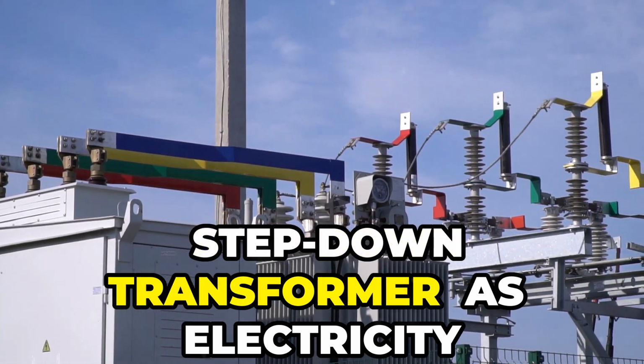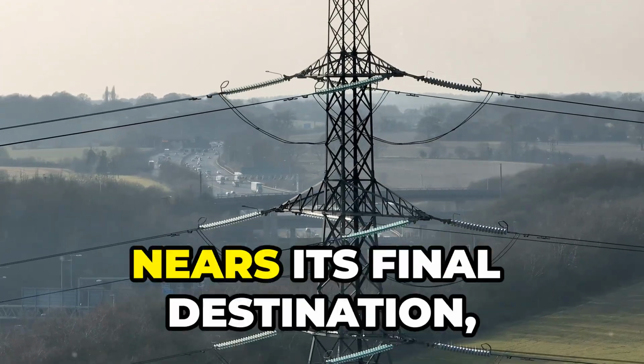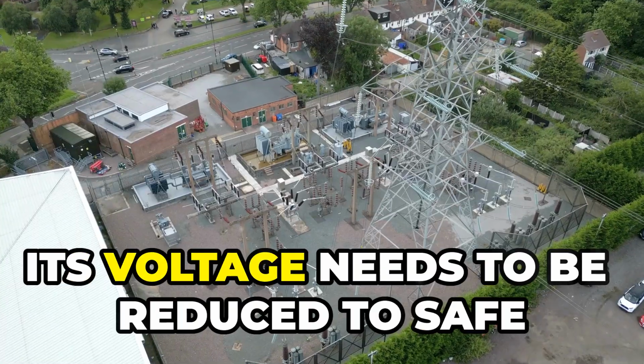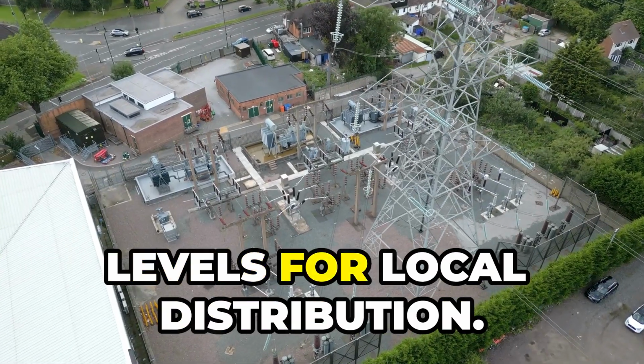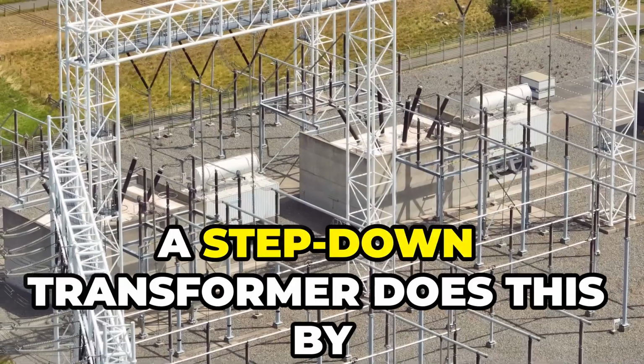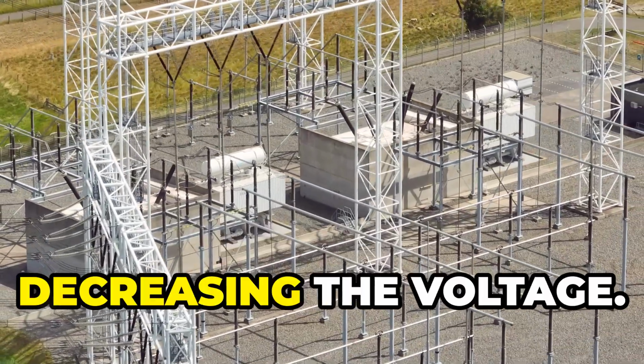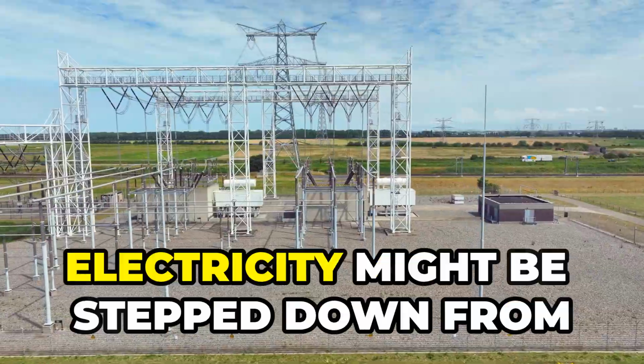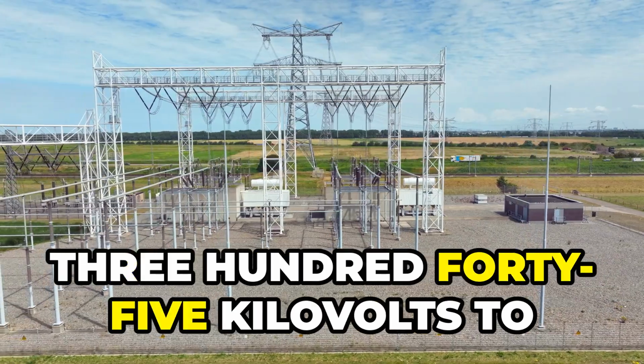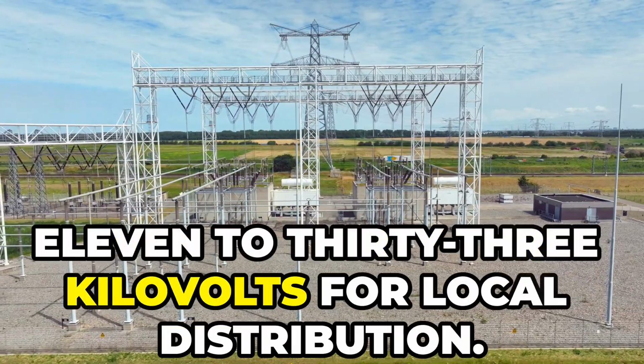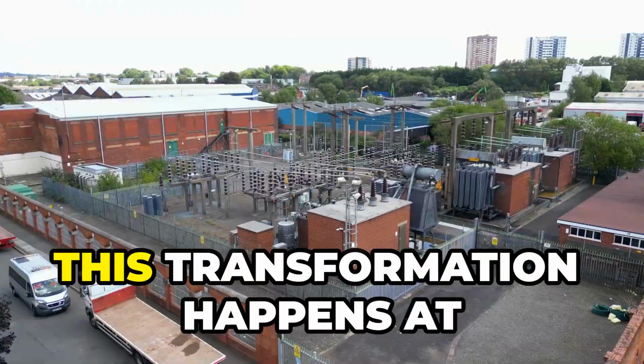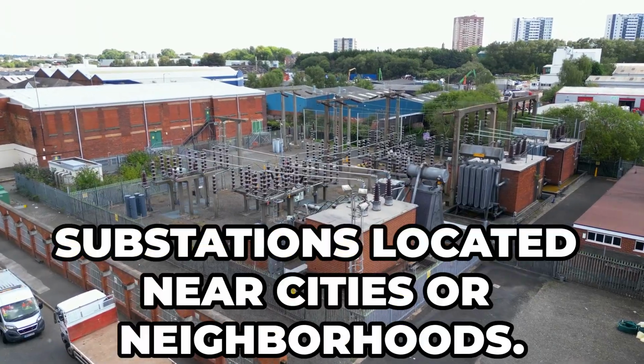Step-down transformer: as electricity nears its final destination, its voltage needs to be reduced to safe levels for local distribution. A step-down transformer does this by decreasing the voltage. For example, electricity might be stepped down from 345 kilovolts to 11 to 33 kilovolts for local distribution. This transformation happens at substations located near cities or neighborhoods.